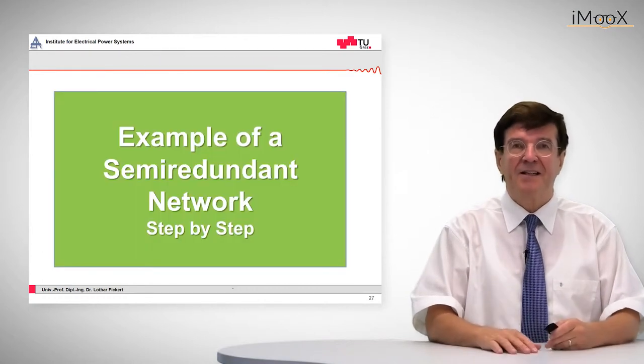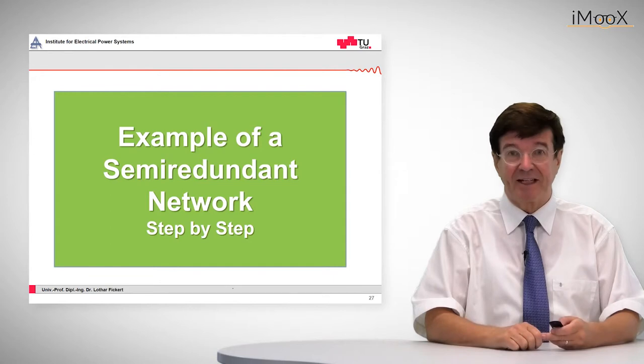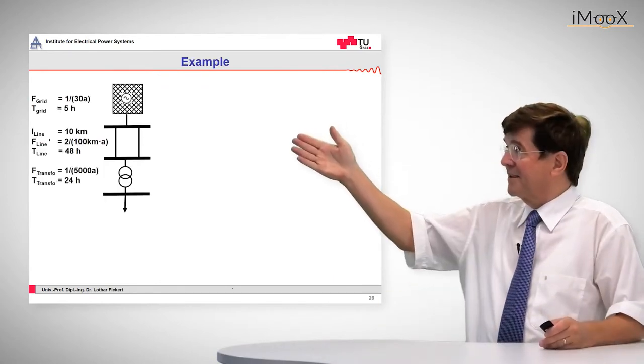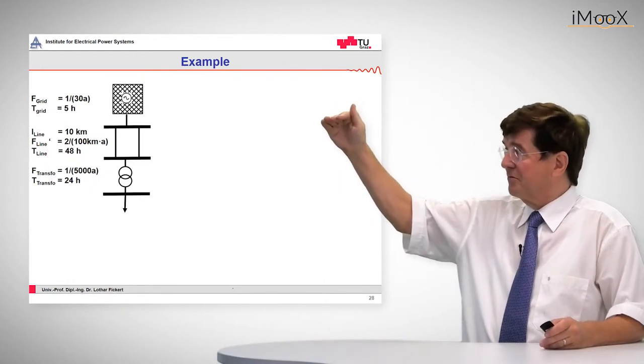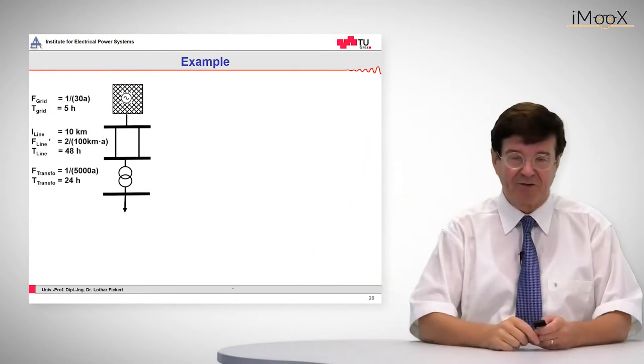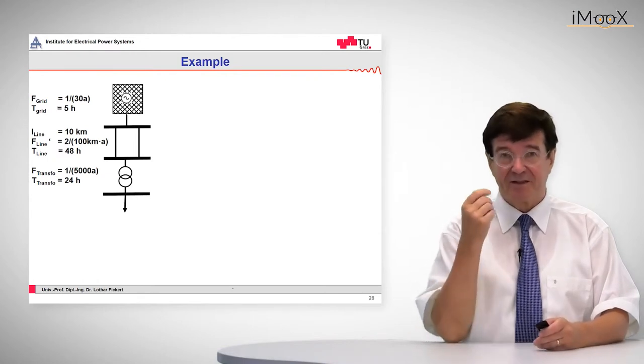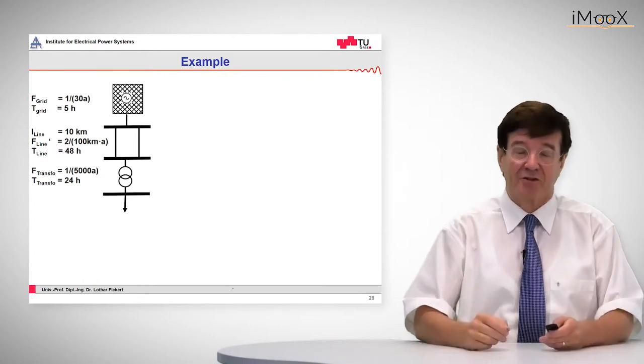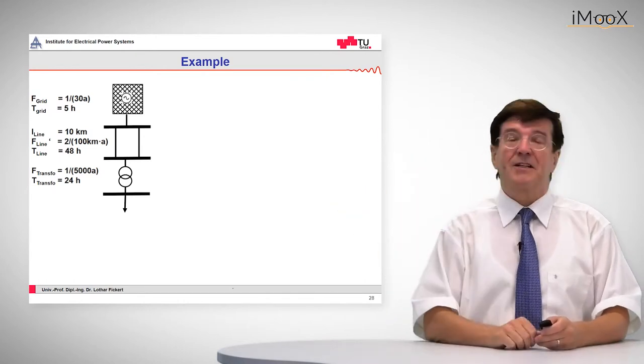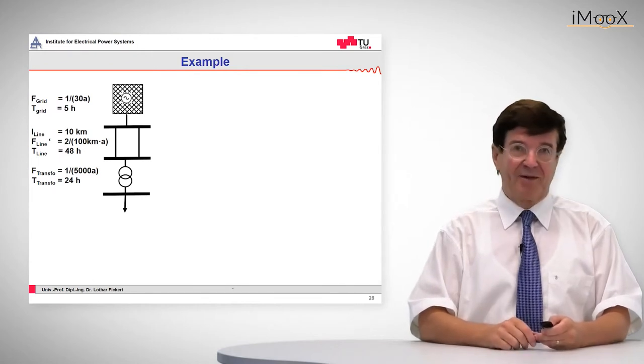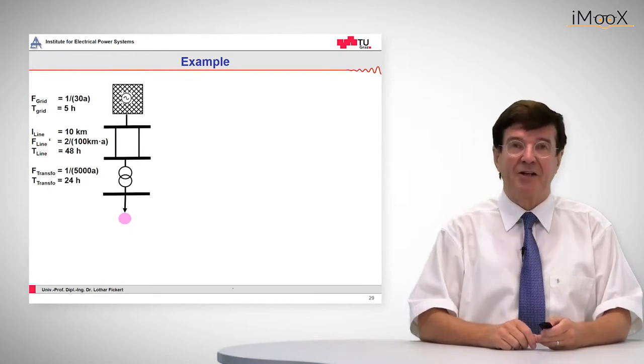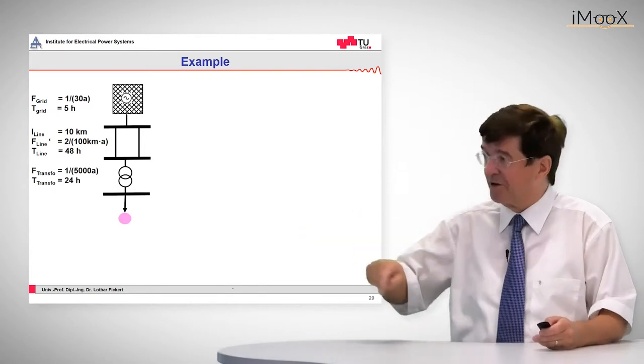Now let's apply this to an example of a semi-redundant network. The network can be seen here: an overlying 110 kV grid with two parallel lines and in series one transformer. It is semi-redundant because we have two lines but non-redundant concerning the transformer. On the left side of each element you can see the average frequency and average outage time. Now we determine the frequency and non-availability at the consumer.